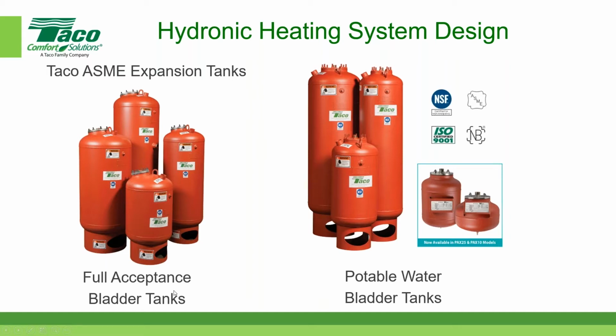Full acceptance means that the bladder can expand to the full volume of the steel container. So for example, if I just arbitrarily say this expansion tank up here that I'm pointing to is 200 gallons, the bladder that's inside that expansion tank, if it fills up with water, can expand to the full 200 gallons of the steel container. That's what we mean by full acceptance. We also manufacture partial acceptance, where the bladder is a little bit smaller than the steel container. They're a little bit less expensive.